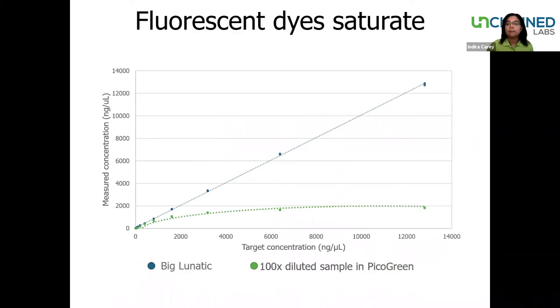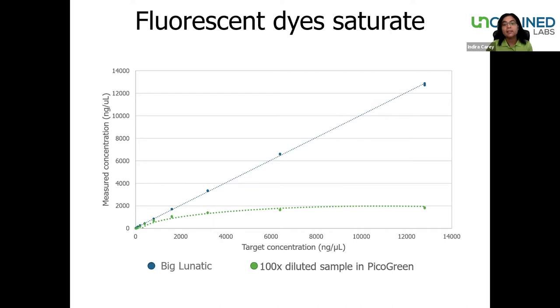Fluorescent methods require that samples fall within the range of known standards, and this can be challenging because fluorescent methods have a smaller dynamic range, which means they saturate easily. In the experiment shown here, you can see the linearity for samples read using Big Lunatic across a wide concentration range, and you can also see the saturation effect with PicoGreen. This curve was generated using the same samples as for Big Lunatic, but the samples were diluted 100-fold. Because of the limited dynamic range with a fluorescent method, a sample might actually have to be diluted multiple times to fall on that standard curve. Lunatic, on the other hand, offers a wide dynamic range with reproducibility and accuracy without the hassle of standard curves and dilutions.